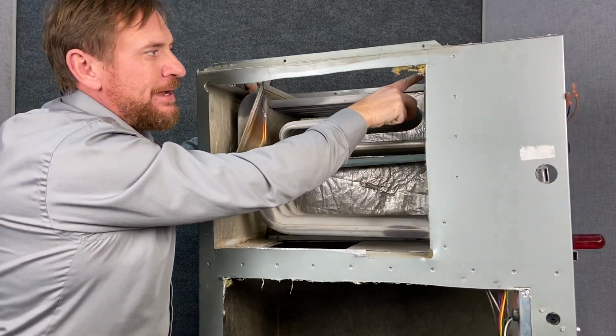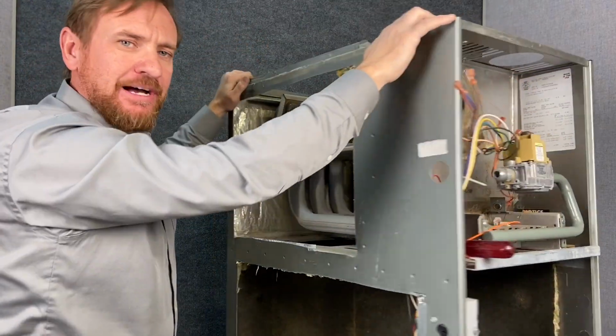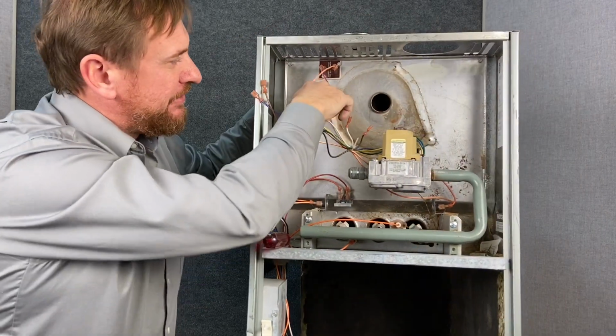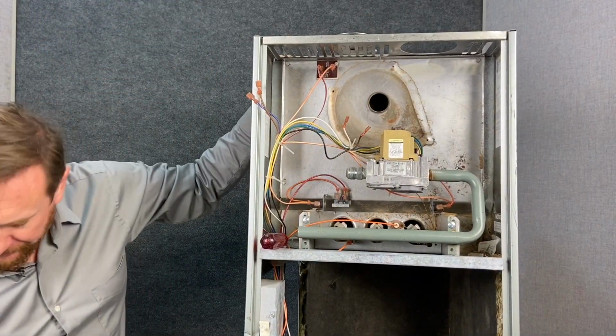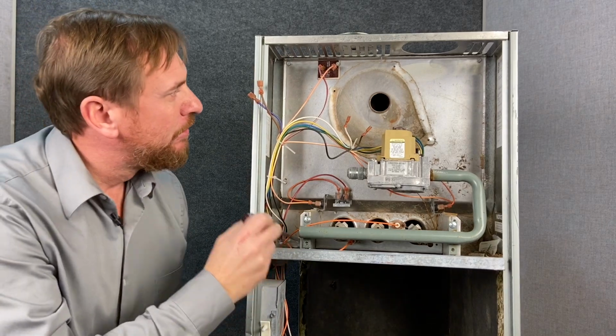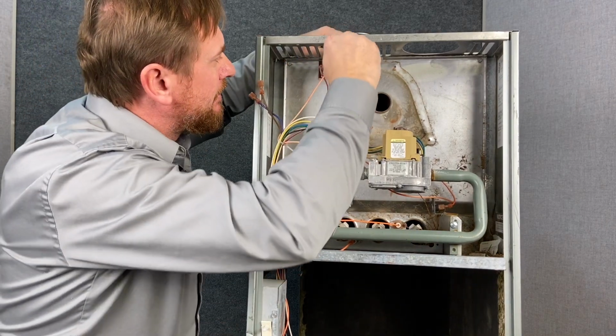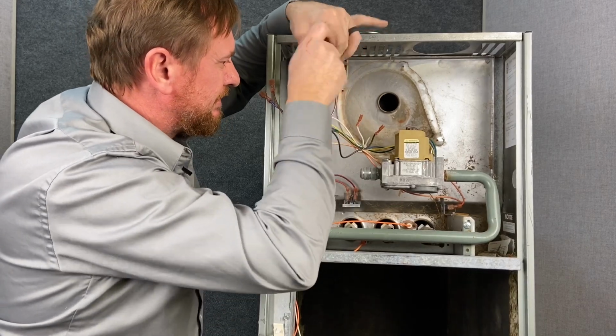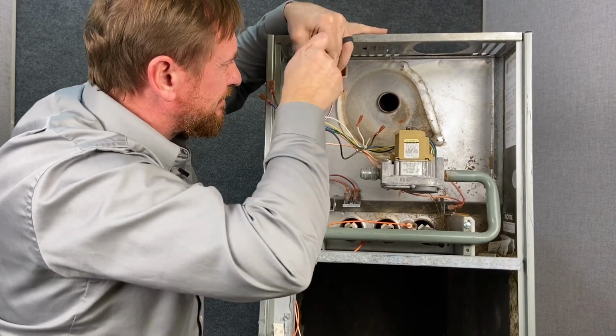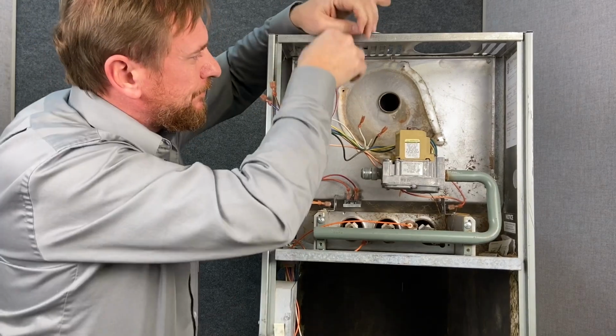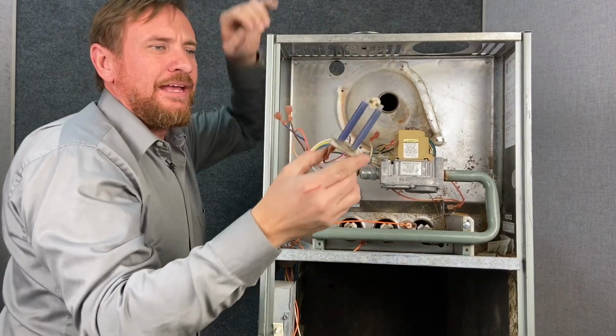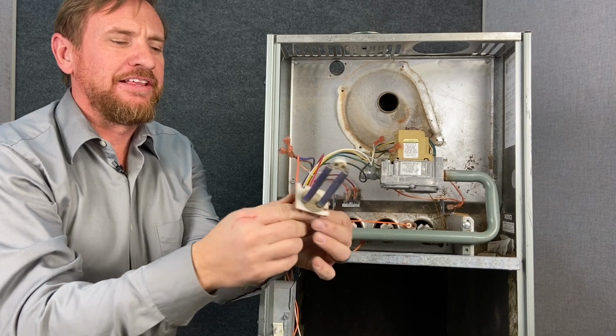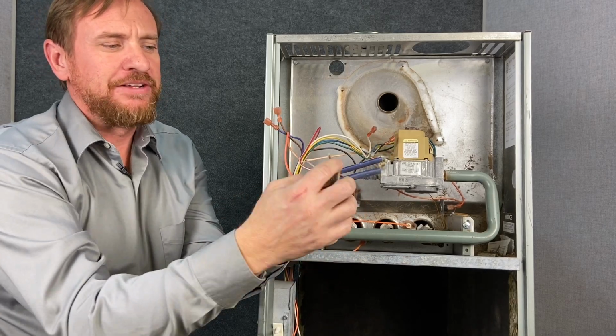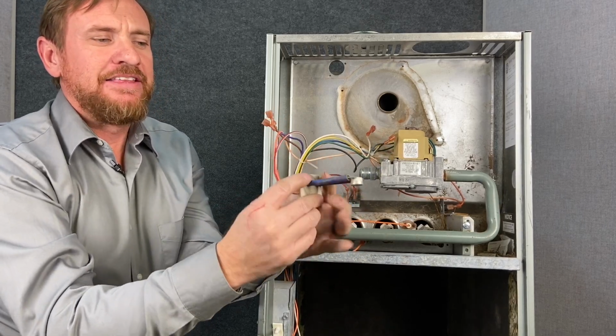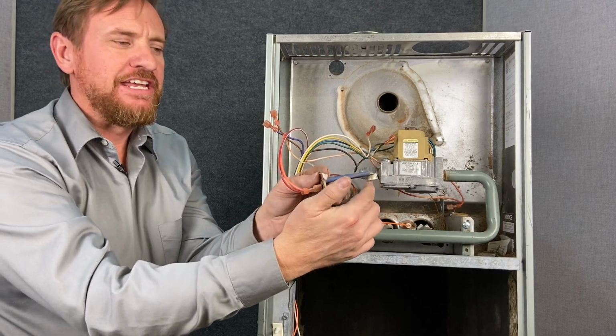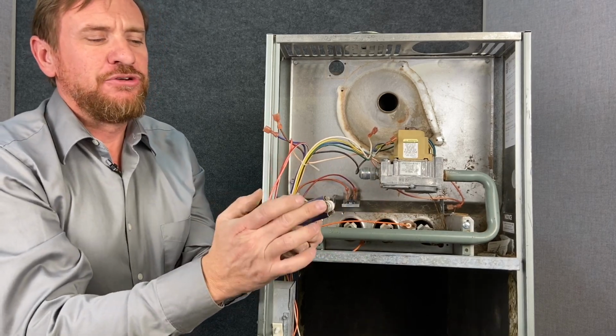So these switches do go bad, especially when you have the evaporator sitting on top of it and it leaks water, and it causes this to corrode out. So what we're going to do is pull this component out so you can see really quickly what it looks like. And here's what our primary limit looks like. This side is going to be on our control panel side. We have this gasket material, and then this is what's on the side of the heat exchanger, on the air side. So if this gets too hot, this trips.